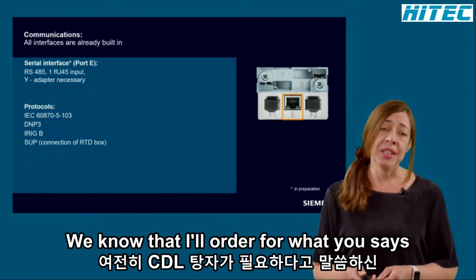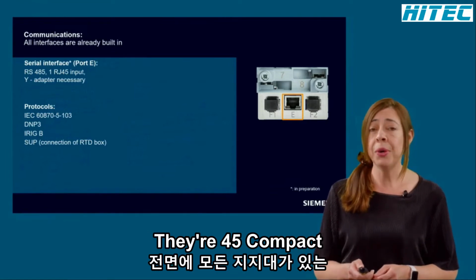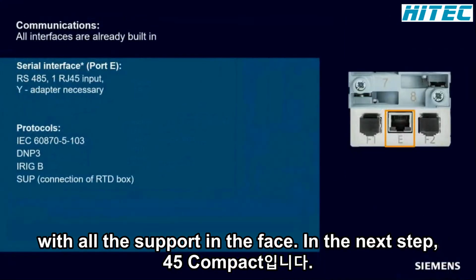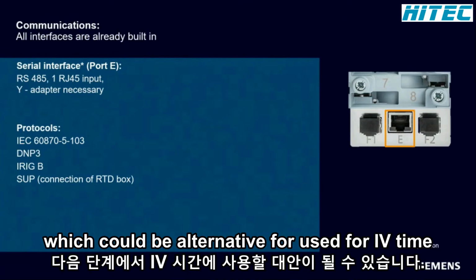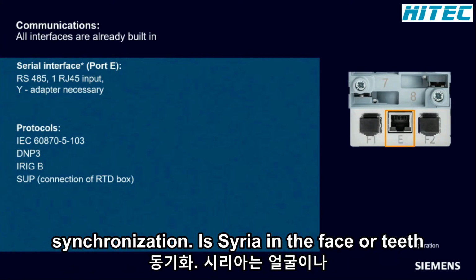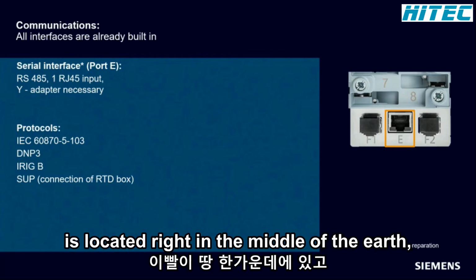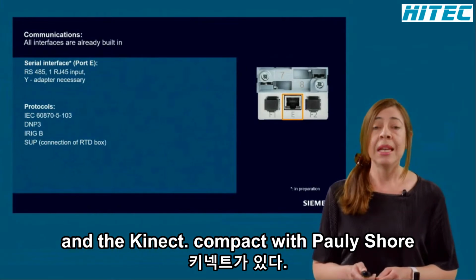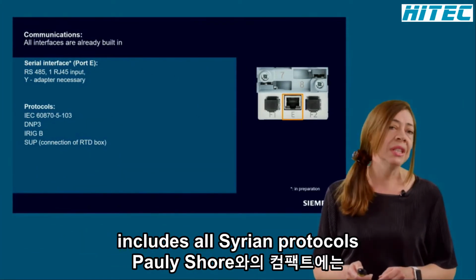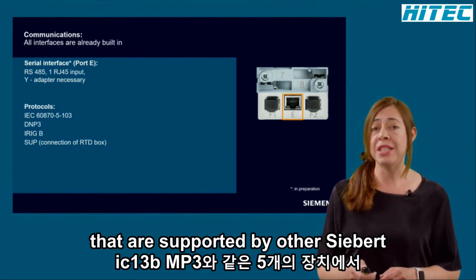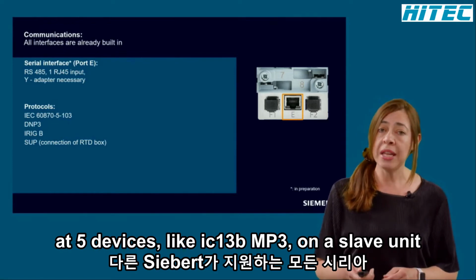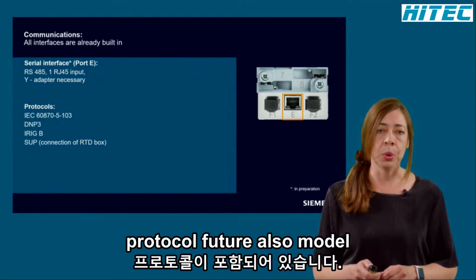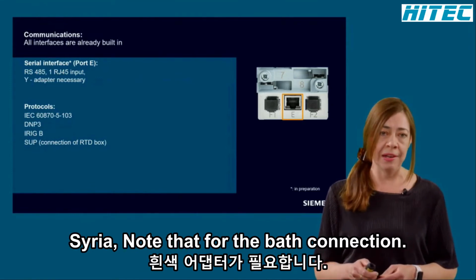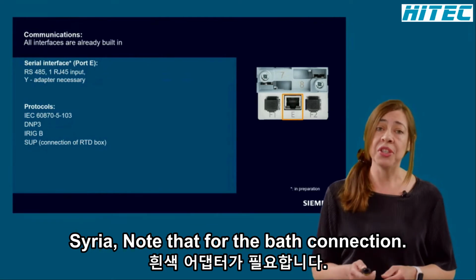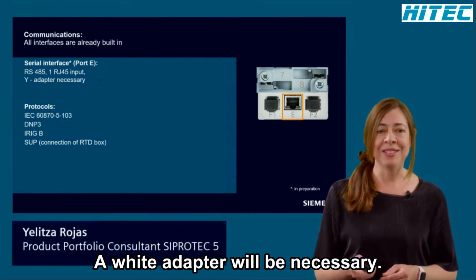We know that a lot of our users still require serial protocols. Therefore, SIPROTEC 5 Compact will also support a serial interface in the next step, which could be an alternative use for IRIG-B time synchronization. The serial interface, port E, is located right in the middle of the Ethernet connector. SIPROTEC 5 Compact will for sure include all serial protocols that are supported by other SIPROTEC 5 devices like IEC 103, DNP3, and slave unit protocol, and in the future also Modbus serial. Note that for the bus connection, a Y-adapter will be necessary.